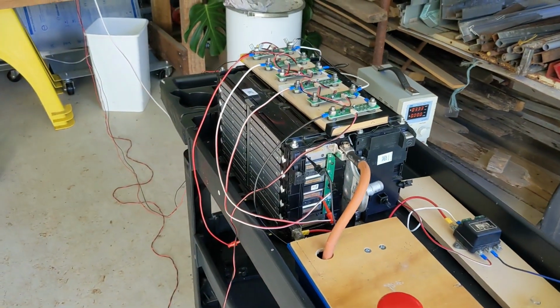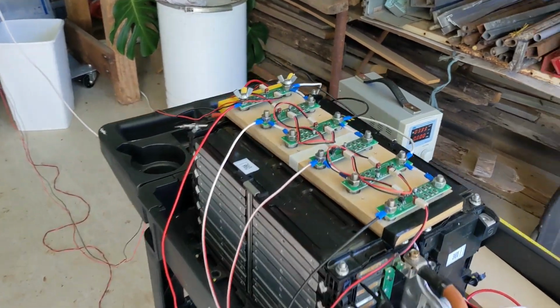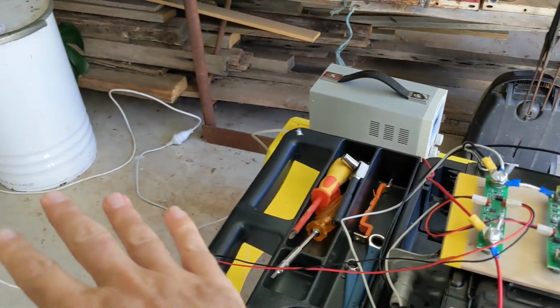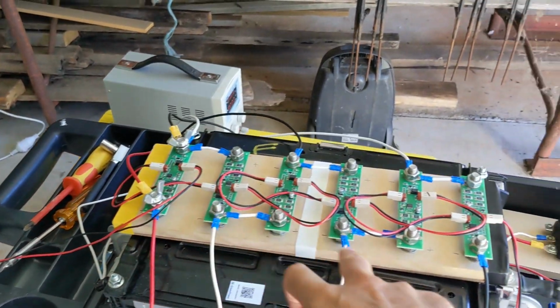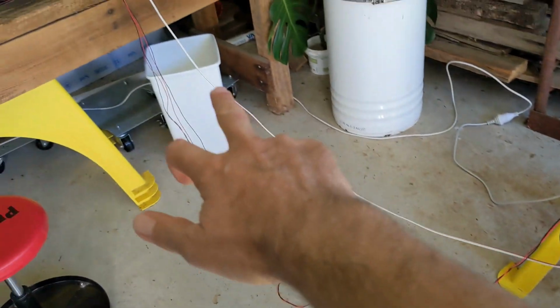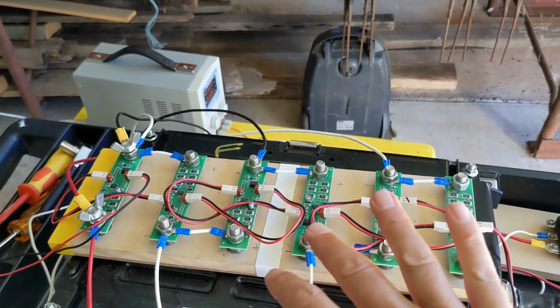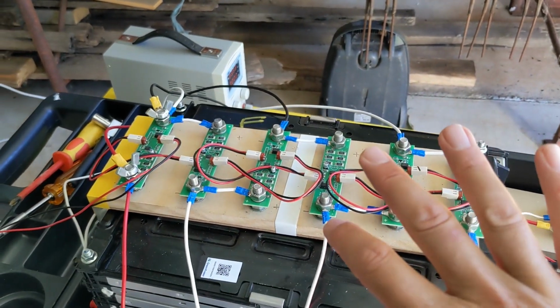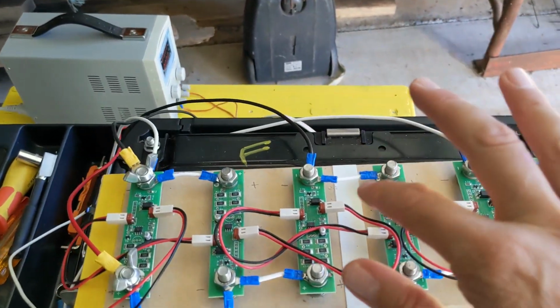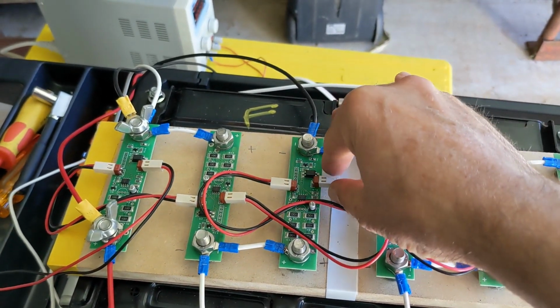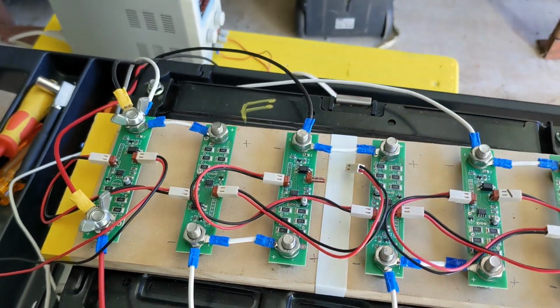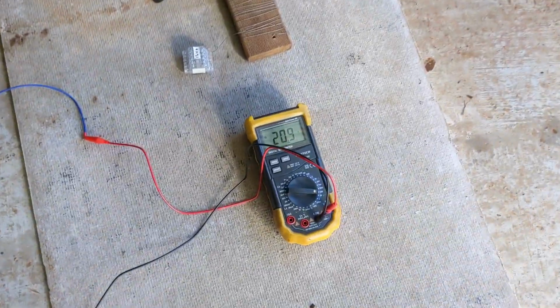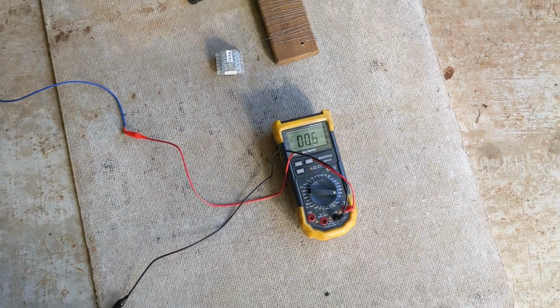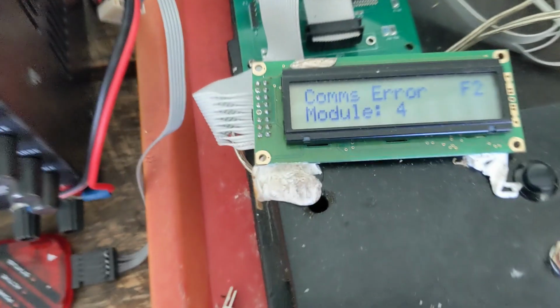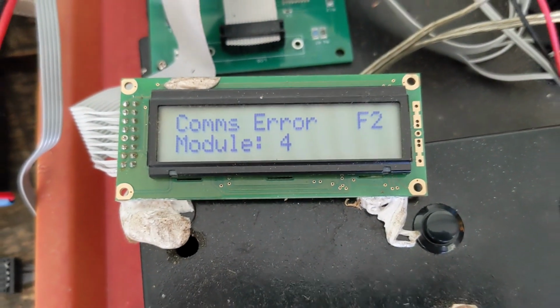The other thing to do is just test out the communication. So the communications runs from the master through one of these wires, through each of these, and then back out and back to the master again. Which means that if we lose communications here, we've then lost our voltage information and we don't know what's going on.